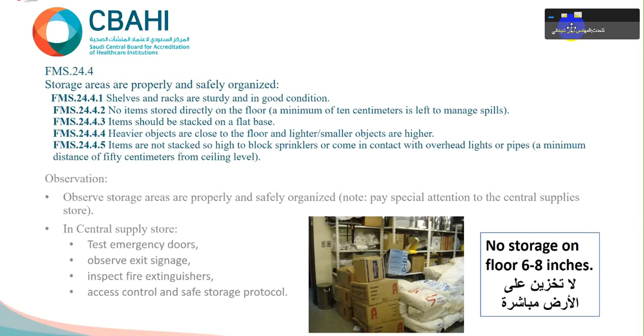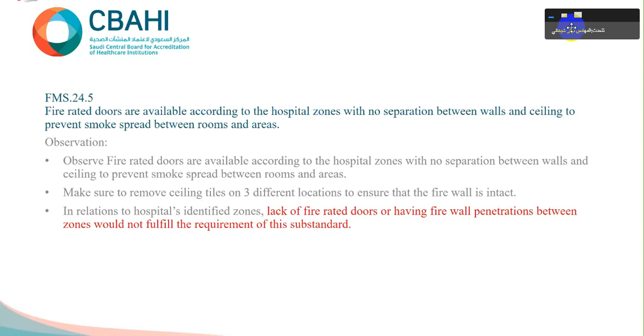Fire rated doors: all fire doors are emergency exits, but not all emergency exits are fire rated doors. During our visit, we inspect 3 different locations. We check whether doors can be released from the magnetic lock, if connected to the fire alarm, and we open the ceiling tiles around the wall between two smoke compartments to check for firewall penetration between zones, making sure there is no penetration for smoke.